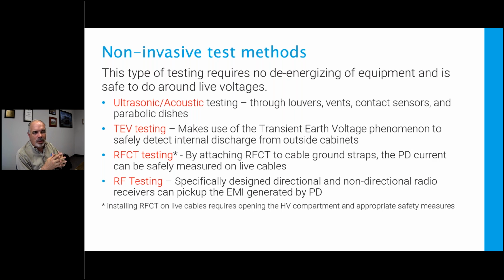TEV testing, we're going to place a TEV sensor on the outside of the cabinets, the outside of the transformer, the outside of the cable. Non-invasive, don't need an outage, can't hurt the cables, can't hurt the switchgear, and it's perfectly safe.